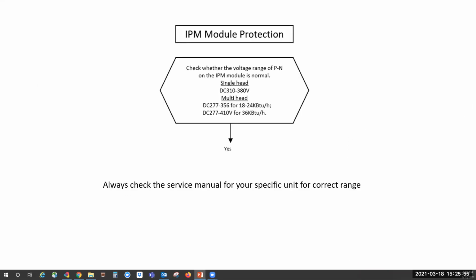So this is where the needle probes off your meter will come in handy. You go to DC voltage. Just flip your meter over to DC voltage. You're going to put your red lead on positive, black on negative. You're going to have this thing powered up, and you're going to see what your voltage is on the P and the N. That's why P and N is so crucial. It's for testing purposes, and you're going to have to refer to your service manual to find out where you're supposed to be at for DC voltage, because it does vary per model and per size.